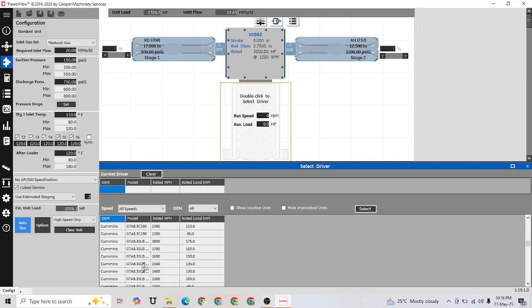Remember, I have to select a machine which is equal to or less than 1200 rpm, and 3000 is the power requirement of this frame. So I have to keep an eye on the rated power as well. I am looking through the options that I have.